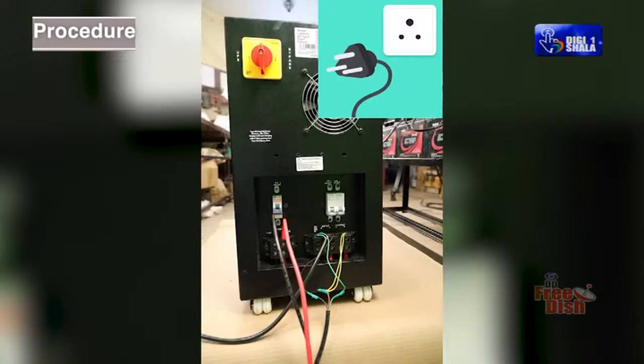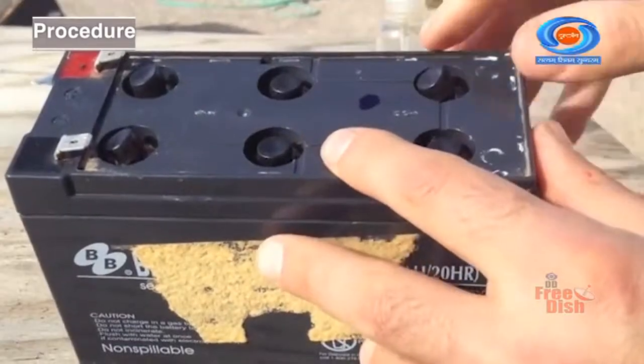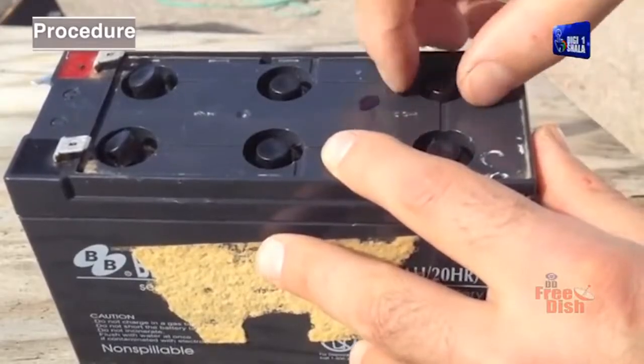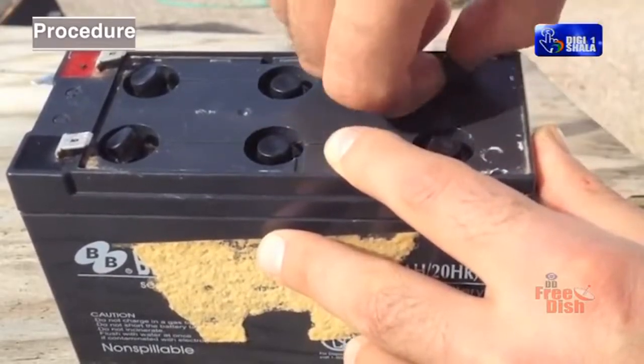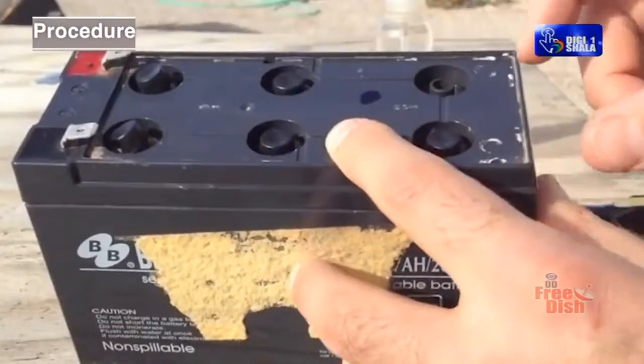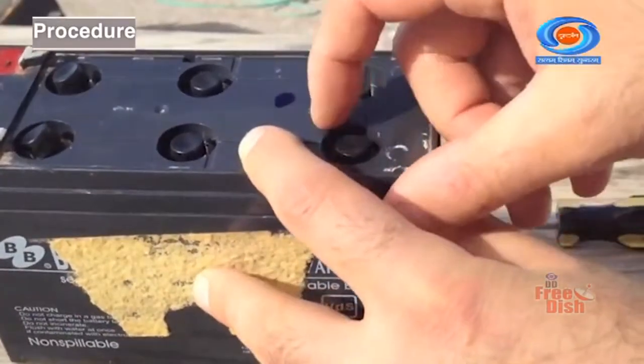Task 4: Replacement of battery. Follow the instruction and procedure below for easy battery replacement. Unplug the unit from the AC power source and disconnect all connected equipment or load. Disconnect the AC power cord from the UPS unit. Turn the unit upside down and unscrew the 4 screws on top of the battery. Keep the screws in a safe place for reassembling.